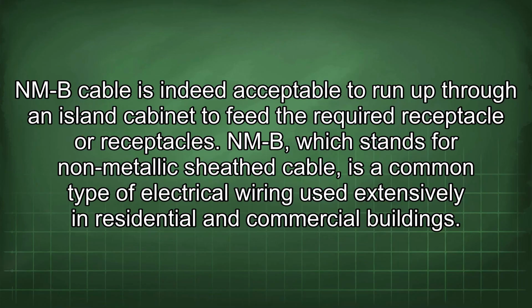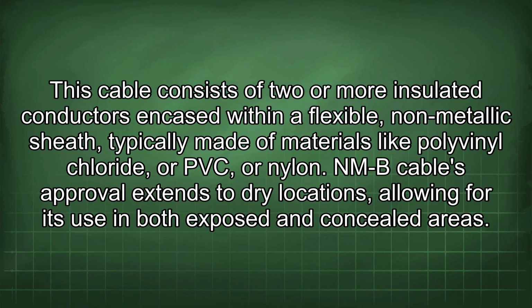NMB cable is indeed acceptable to run up through an island cabinet to feed the required receptacle or receptacles. NMB, which stands for non-metallic sheath cable, is a common type of electrical wiring used extensively in residential and commercial buildings. This cable consists of two or more insulated conductors encased within a flexible, non-metallic sheath typically made of materials like polyvinyl chloride, or PVC, or nylon.